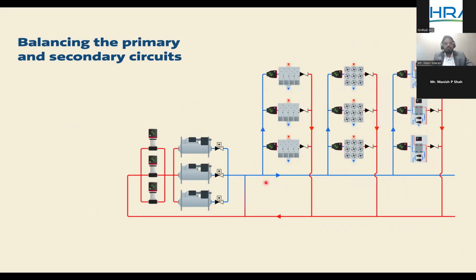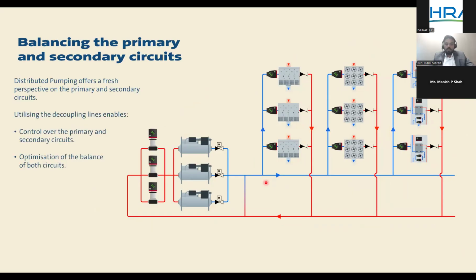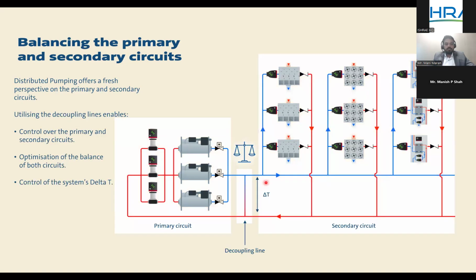Let's see a little bit of the balancing side, how we balance primary and secondary, how we control the flow on the secondary side, how we control the flow on the primary side. So as I said, we have a primary loop, which is a production loop. We have a secondary loop, which is a distribution loop.